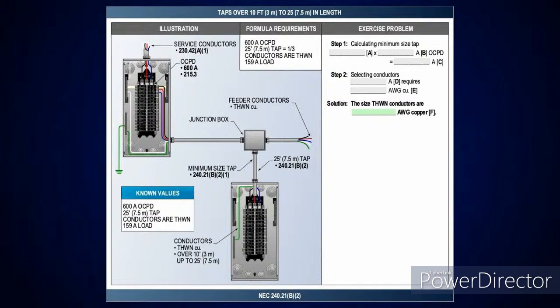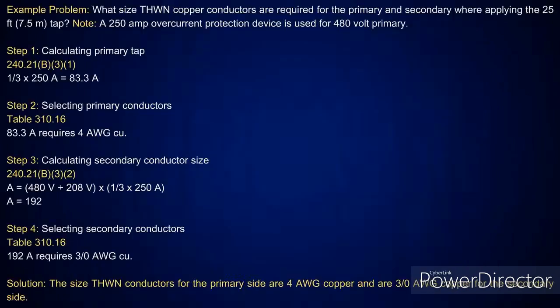But when people get over this, this is just like the 10-foot tap. The only difference is we did a 25-foot tap. Same type of overcurrent protection device. Instead, you're just taking it at a third. So nobody should have a problem sizing that.